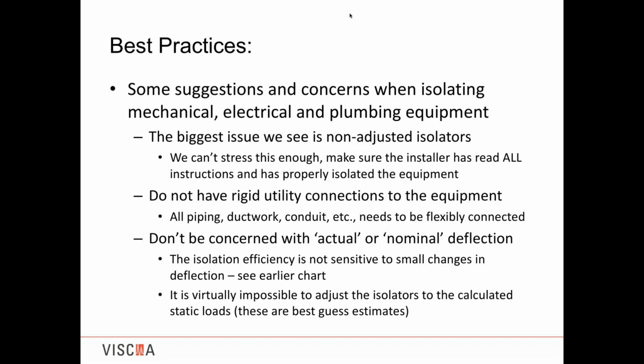And I'll repeat again on this slide, don't be concerned with the actual versus nominal. The isolation efficiency is not sensitive, and it's impossible to adjust the isolators to get the calculated static loads. If you think about any system installed on 4 springs, in any free body diagram, that is effectively an indeterminate reaction system. I can adjust those springs and have an infinite number of reaction combinations. If they're all adjusted roughly equally per the instructions, you'll get roughly the load that was estimated.